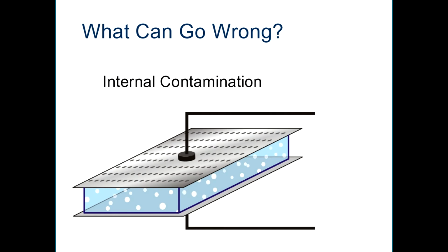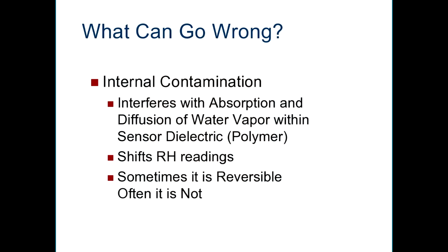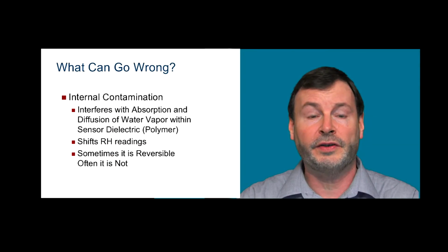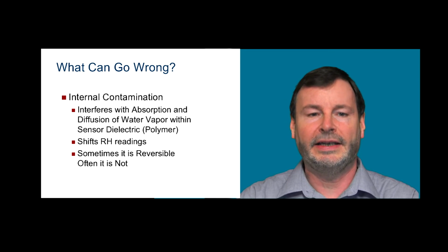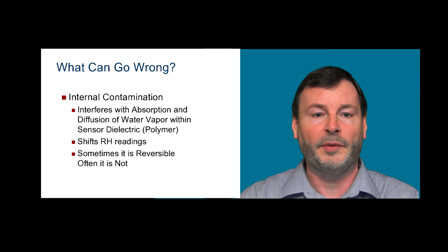Now, internal contamination occurs when various chemicals or contaminants have entered the dielectric or the polymer of the humidity sensor. These could be cleaners or volatile organic compounds, for example. This contamination interferes with the absorption and diffusion of the water vapor within the sensor, and it shifts the RH readings, sometimes by quite a significant amount. Sometimes this can be reversible by heating up the humidity sensor and essentially boiling off the contaminant, but usually it doesn't reverse, at least not totally, because the polymer has been damaged or altered in some physical way.